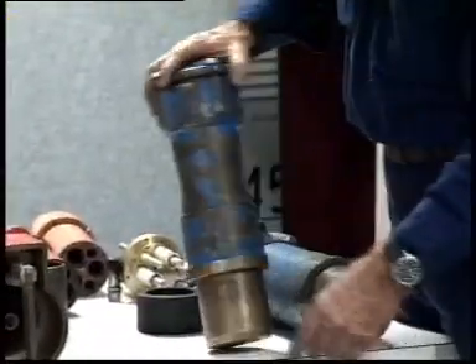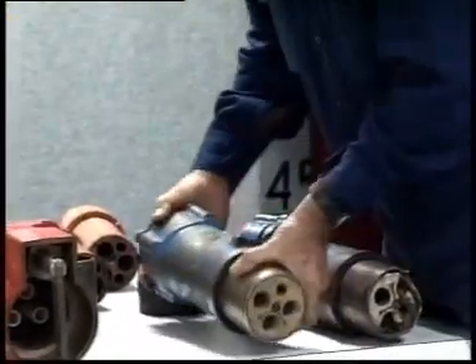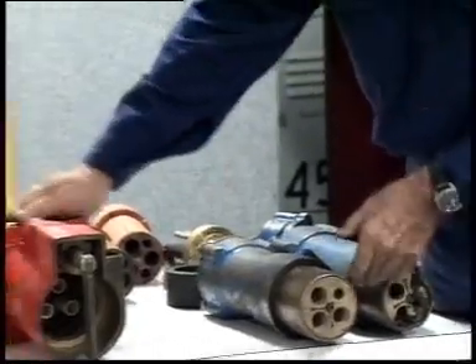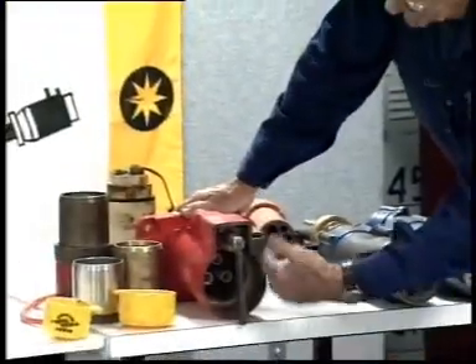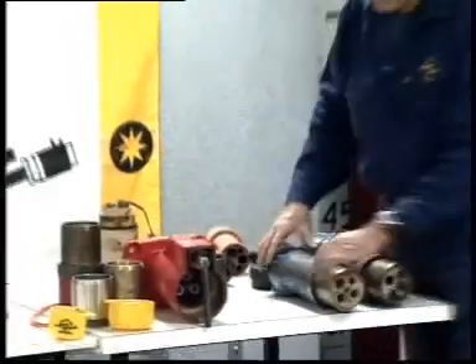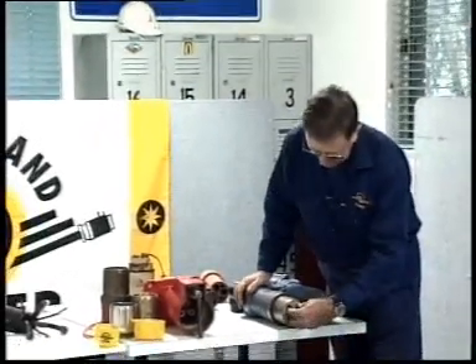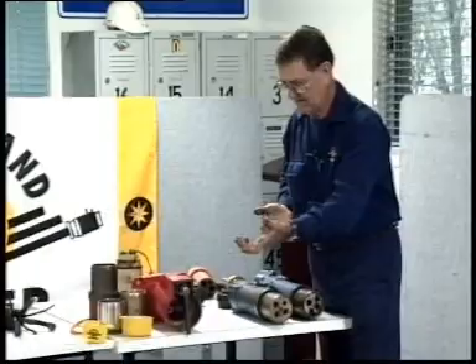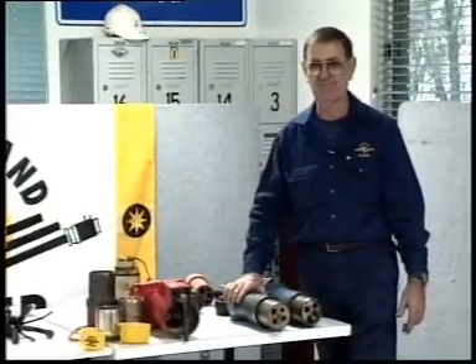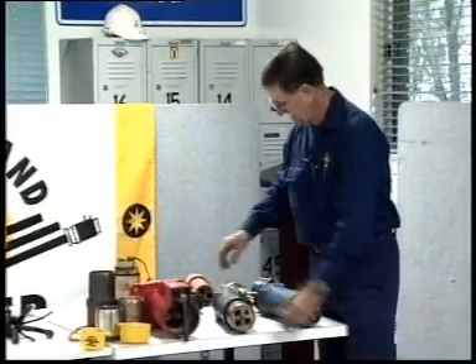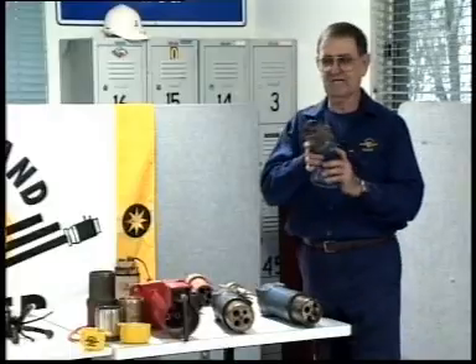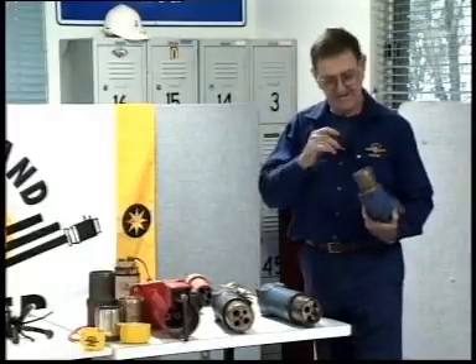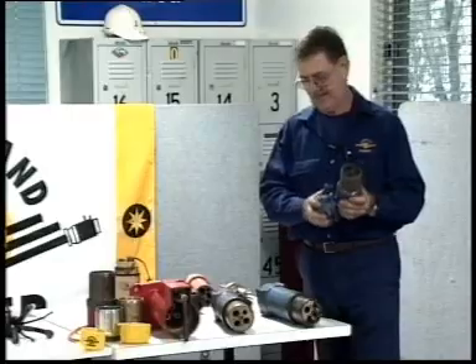All things being equal, we've made sure the power's off. We've checked and made sure this is firm enough. Looked up there, and it looks reasonable and clean inside. Flame path looks pretty good. No crap up here, no burnt pins. Away we go. Same thing applies to your banana plug. Exactly the same thing again: flame path, interior, and the clamp on the back.